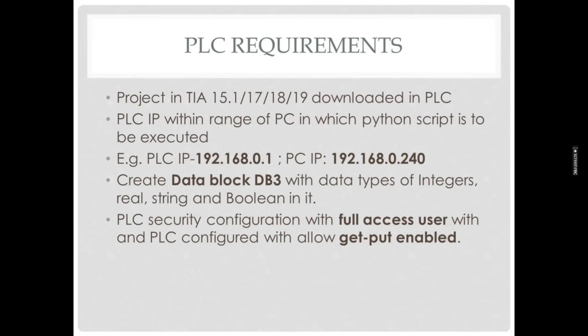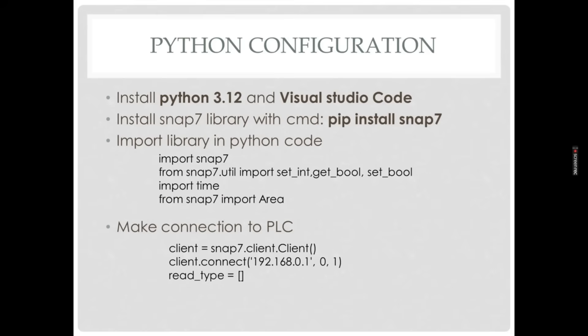In the PLC we need to create a data block. For example, I have considered DB3 with data types of integers, real, strings, and boolean. In the PLC security configurations, we have to create a user with full access, and then we need to enable get/put in the PLC.